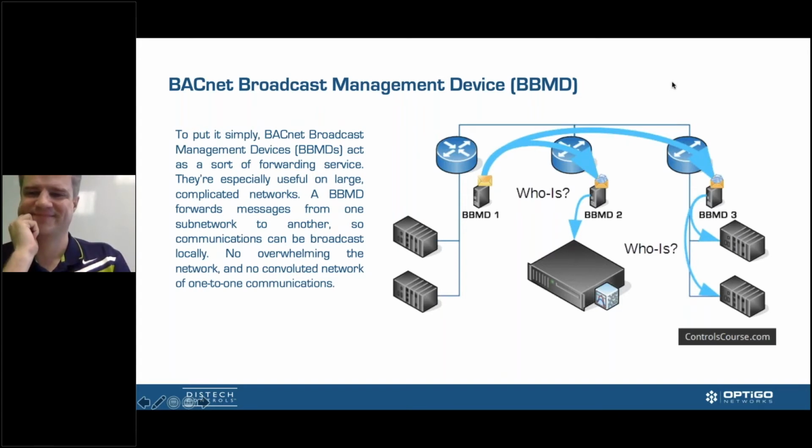If you identify each of them to one another, you can set a network value or an outside air temp to be written into another controller on a different VLAN. You don't need a BBMD for that at all. The BBMD is simply needed for broadcast traffic. So things like a time sync to the network, a discovery, COV broadcast, if you're broadcasting a single value to an entire network, that's where you'd need a BBMD.